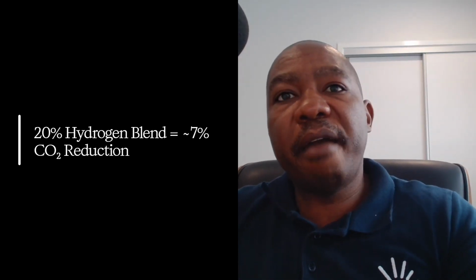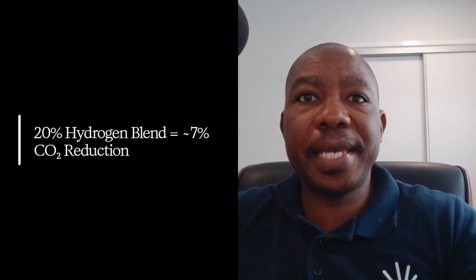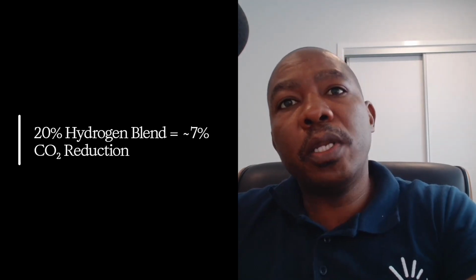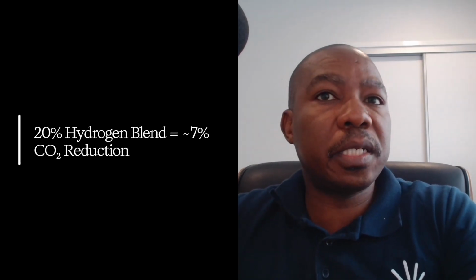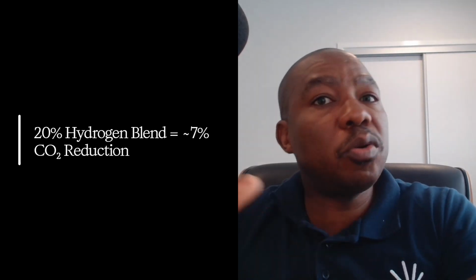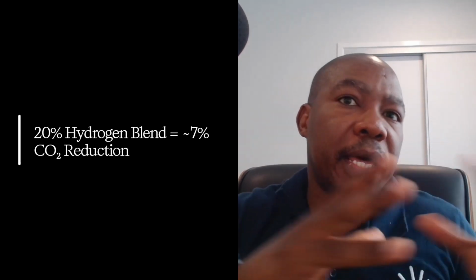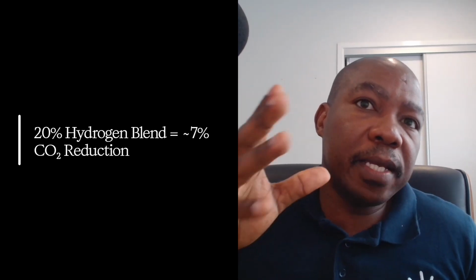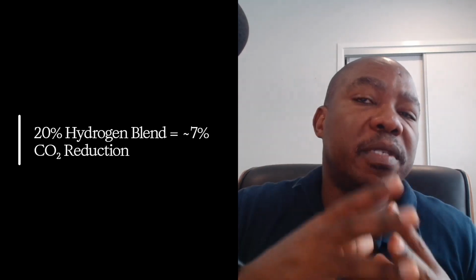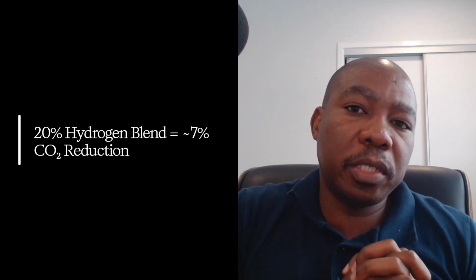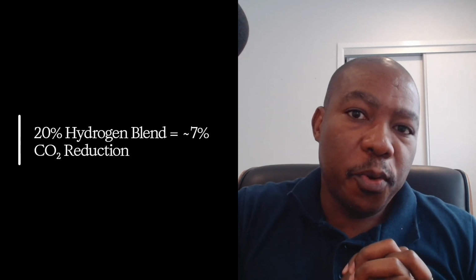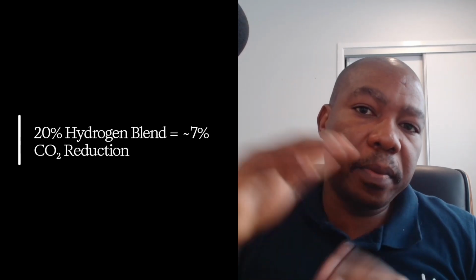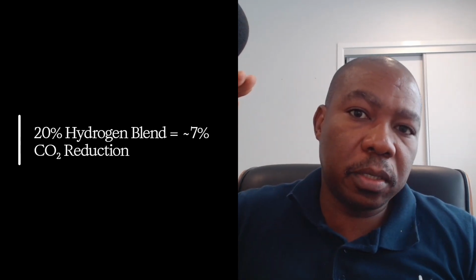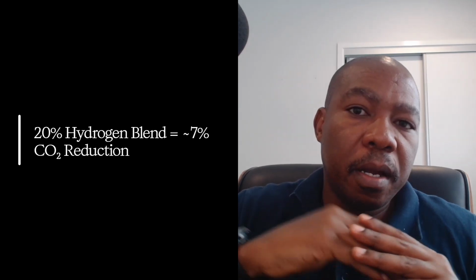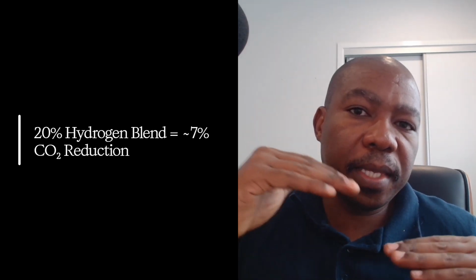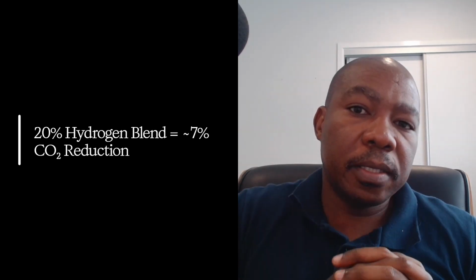So with the effort that we've put in, 20% hydrogen, only to gain a 7% reduction in CO2. And this is consistent. This is not something that we made up here. This is a natural observation of what hydrogen blending actually does. We go up in the hydrogen purity, so to speak, but we only get about 7% CO2 reduction.